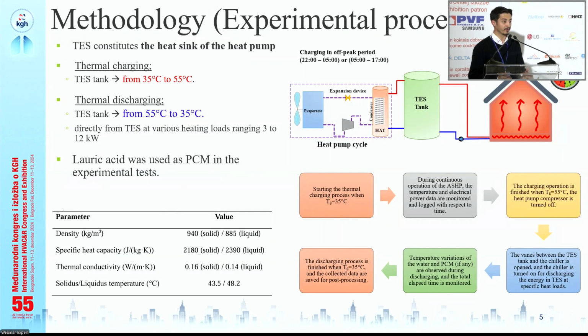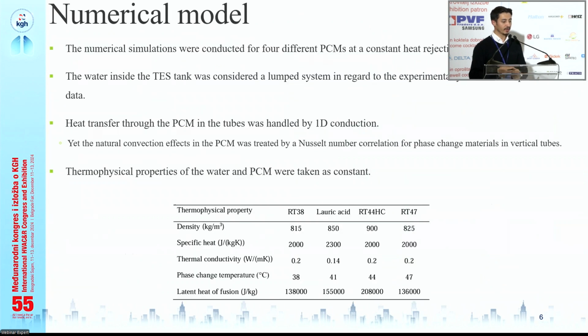because of its favorable thermophysical properties, which are shown in the table. It is suitable for the temperature range we operated, because the phase change temperature should be between the upper and lower limits of our heat pump operation, actually the thermal charging and discharging temperature limits. Besides, it is also a well-known material for thermal energy storage, and it is cheap and easy to find. The numerical model was conducted for 4 different PCMs, because once we establish the model, it is easy to implement other PCMs in the model. But we held the heat rejection rate at 3 kilowatts to make the comparison simpler, though it can also be another parameter.